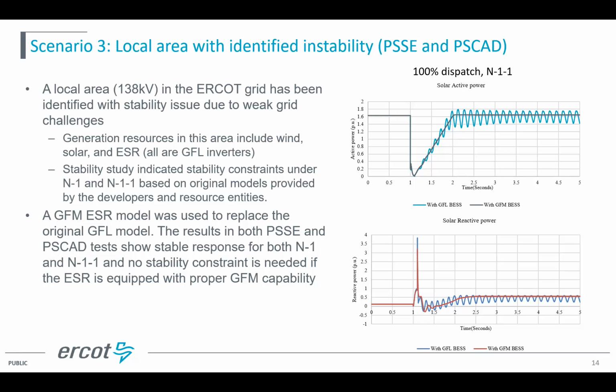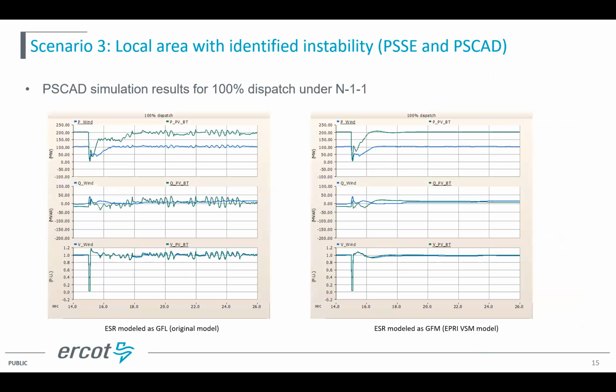The top right one, and also the right side, basically shows the PSSE simulation result for the N-1-1. As you can see, if the battery is the original grid following model, there's sustained oscillation. I think the frequency is also 6 Hertz, kind of similar to our WECC test case. Then with grid forming, the oscillation goes away. So this is the PSSE simulation. We also performed the PSCAD simulation. The left side is the original model and the right side is the grid forming model. On the left side, the original model shows some oscillation, and on the right side with grid forming, the oscillation goes away and it is stable. This is based on the EPRI model. As I said, if we plug in the PNNL model, the response is kind of similar.